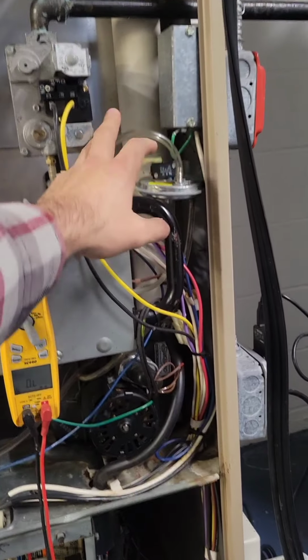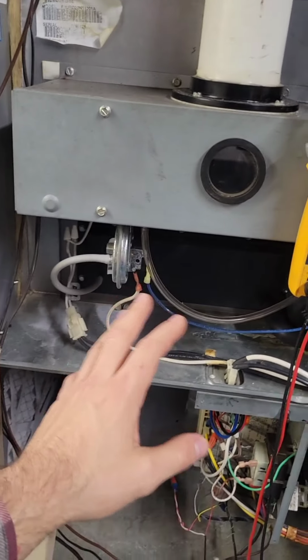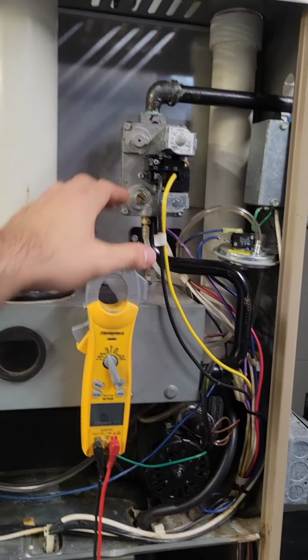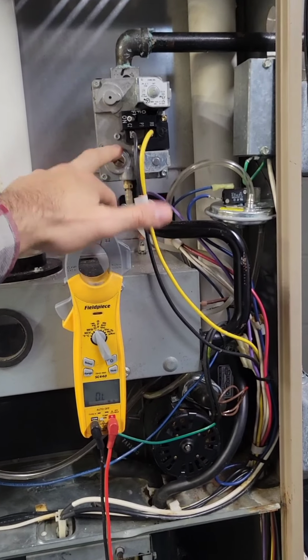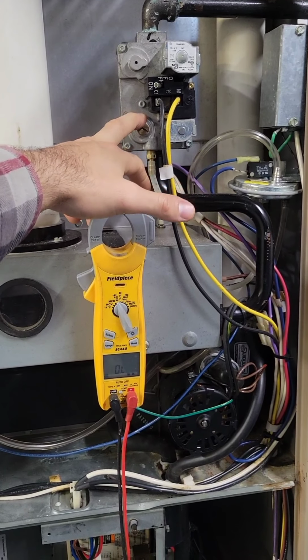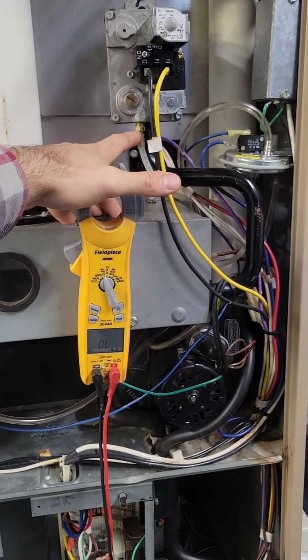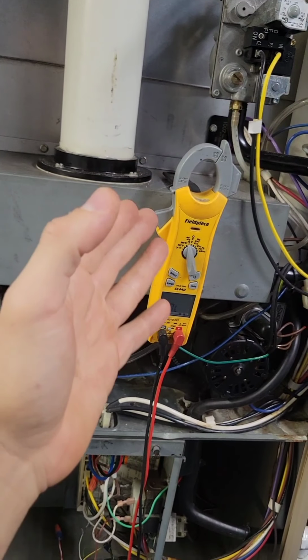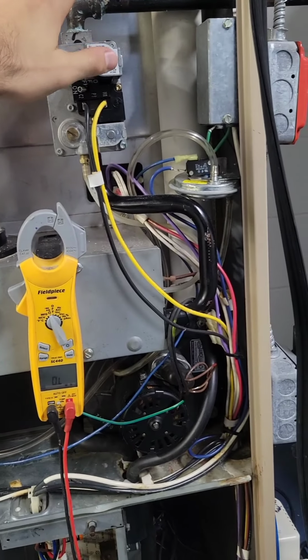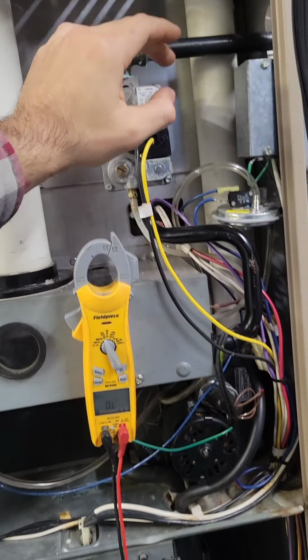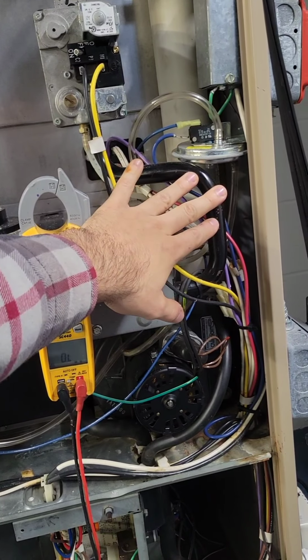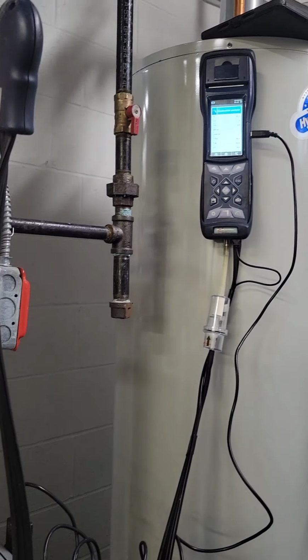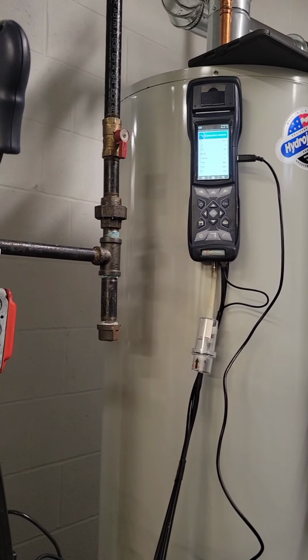Like I said, we check pressure switch hoses, both positive and negative. We also like to check the fuel. We check to make sure we have the proper inches of water column at both the manifold and the incoming. So incoming will be here before the gas valve. Your manifold will be here after the gas valve. So those two areas we check out. And that little buzzing you hear over there is actually my combustion analyzer, because I want to make sure that we're burning the fuel properly.